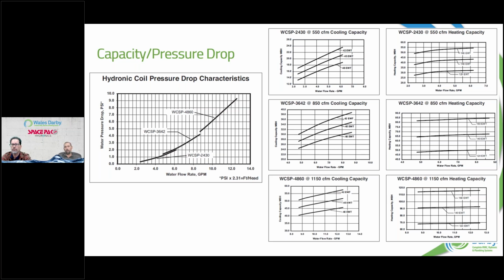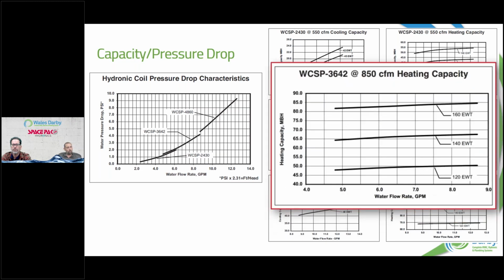We need to see a load calculation. We've got to have that Manual J, and then we can look at our emitters and see, based on the water temps we want, are we getting the BTUs to deliver, right? It's not so much the water temp, like we're going to discuss next week, it's BTU delivery. So these charts will help you out. There you go. I should have done that the first time. Let's just click one more.